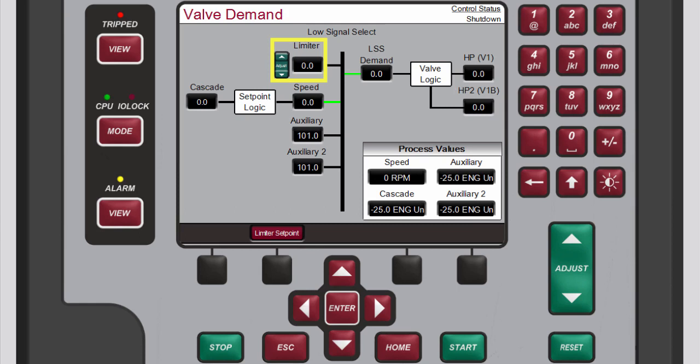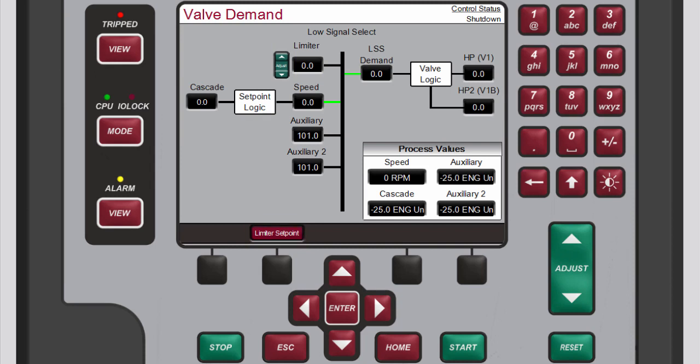During normal operation, the valve limiter setting is at 100% and not limited. Typically, the only time this parameter is adjusted is during a start sequence or to troubleshoot system dynamics problems. The menu bar provides access to the valve limiter setpoint and, if configured for use, the manual valve demand.